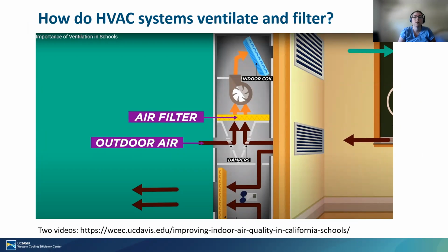So just on a real practical level, how do we ventilate and filter a classroom? The simplest form is we have an HVAC system. Now it could serve one classroom, it could serve multiple classrooms, but the most common type of system is essentially a package type system, particularly in California. And so we basically get your return air back from the room. Some of it gets dumped outside. You mix in some outdoor air. So these two air streams mix. They go through a filter, they go through a fan, and then they go through your cooling coil or your heating coil or your furnace, and then they get conditioned and supplied to the room.